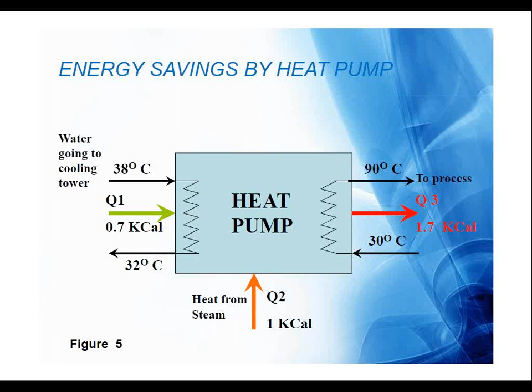This is a typical presentation of vapor absorption chiller versus vapor absorption heat pump. In the vapor absorption cycle also, there are 3 types of streams. One is the application stream, which is chilled water. If we consider this as Q1, and the other stream, which is live steam, live heat, as Q2, as a principle of refrigeration, this Q1 plus Q2 should get rejected into the cooling water system, that is Q3. So Q3 is nothing but Q1 plus Q2.